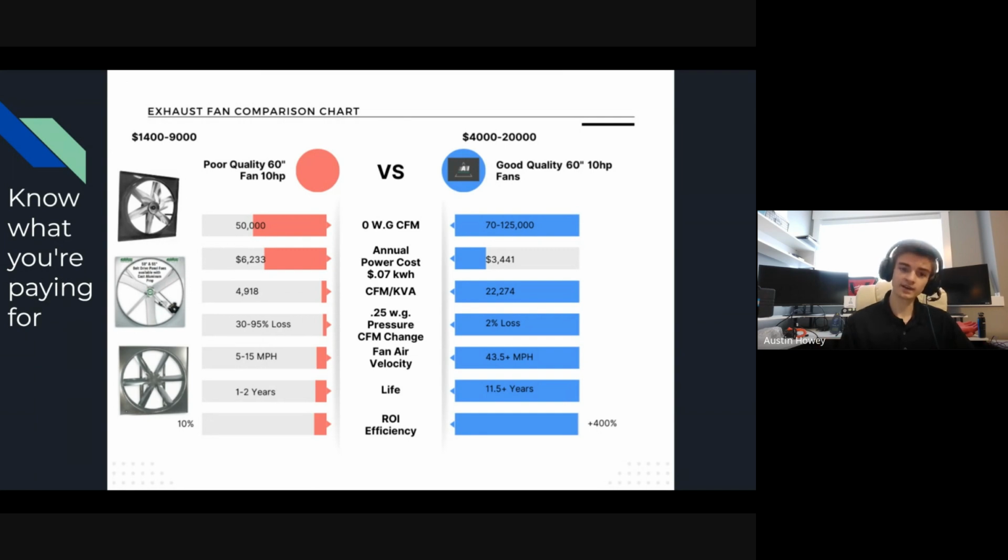The other fan that's really bad is the plastic fan. I see a lot of people buy greenhouse fans or J&D fans, or things like Utilitech, Menards fans, any type of fan that's designed pretty much for residential use or just light duty use. Those aren't going to last you very long just because of the way that it's designed.